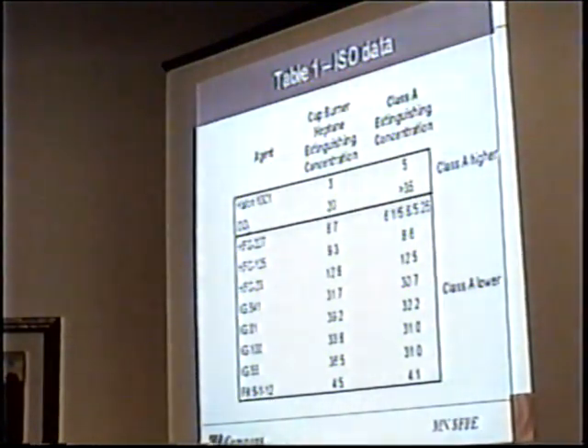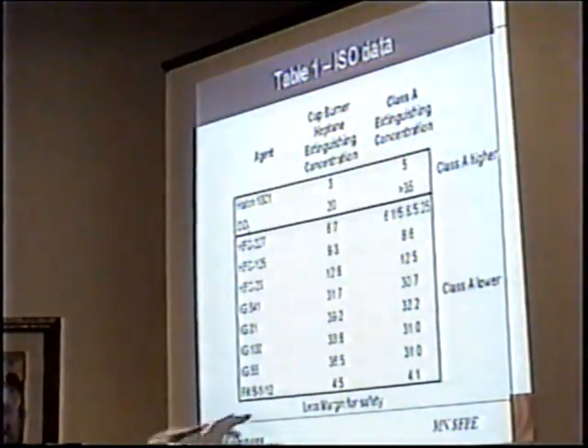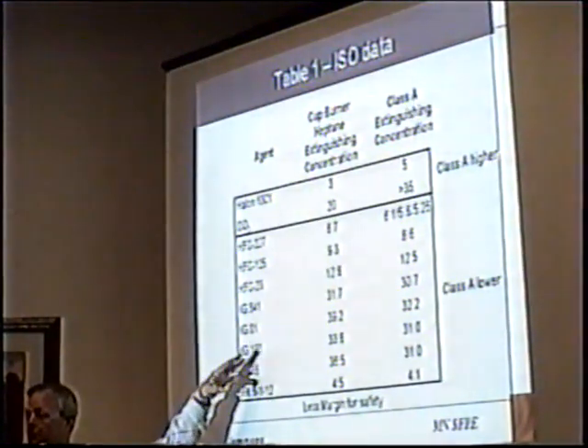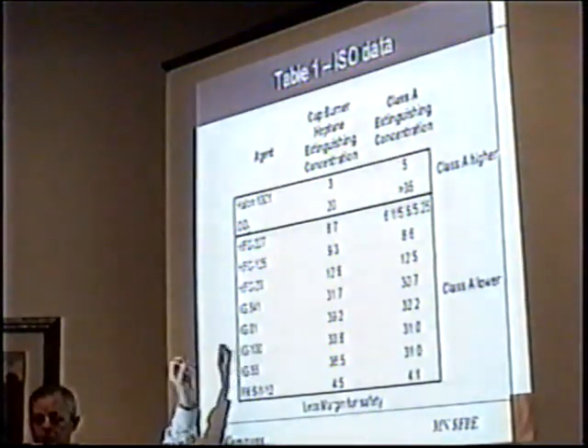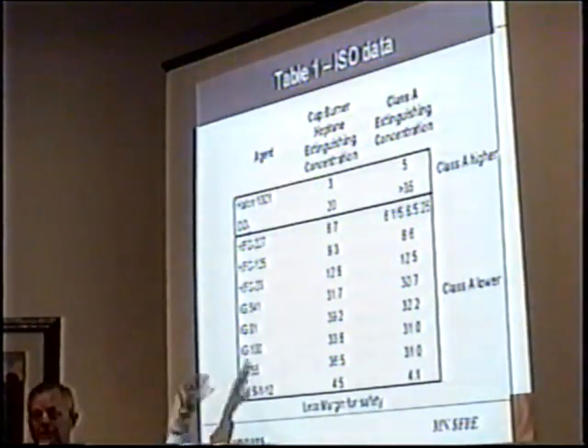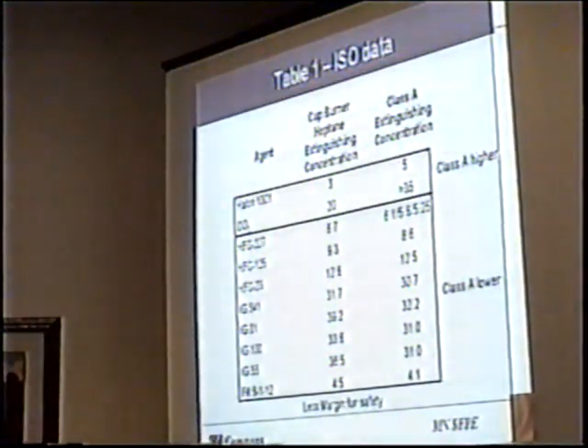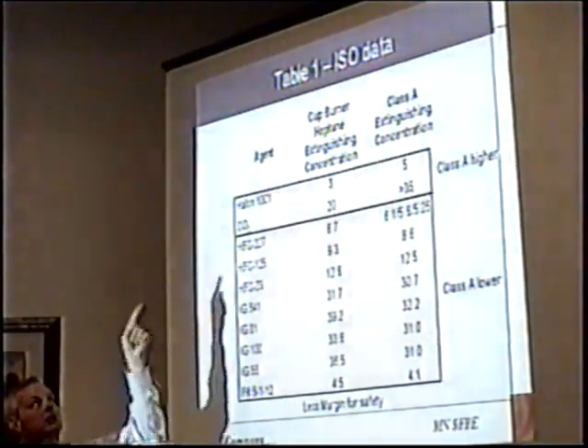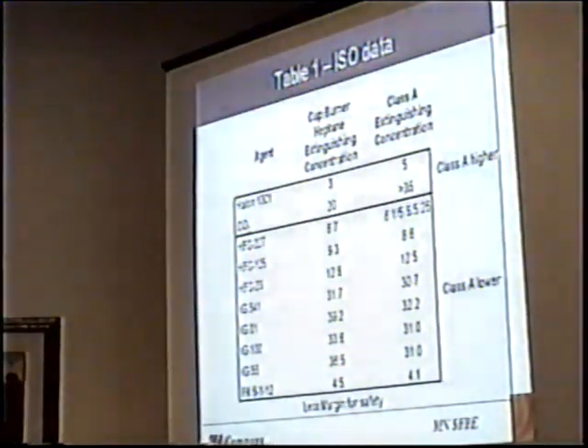So what we have is less margin for safety, less confidence by the standards organizations, UL and Factory Mutual, that they would work. That's why the criteria for passing the test were higher than they were for Halon and CO2. 30 seconds for extinguishing as opposed to 1 minute, for example, that type of thing.